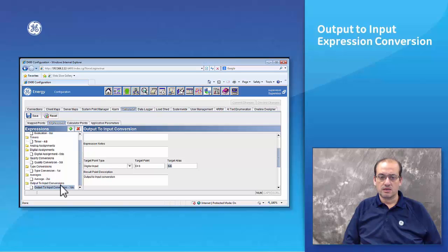The way it's done is we make a digital output available to both masters, and when one master basically forces that digital output, that's a message that gets converted into a digital input, and that digital input can be retrieved or polled, if you like, by the second master.